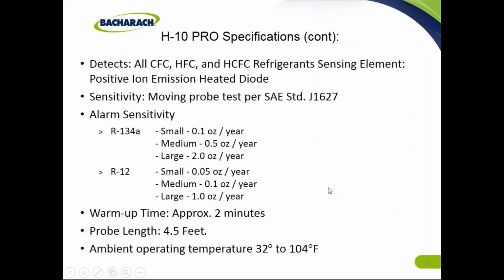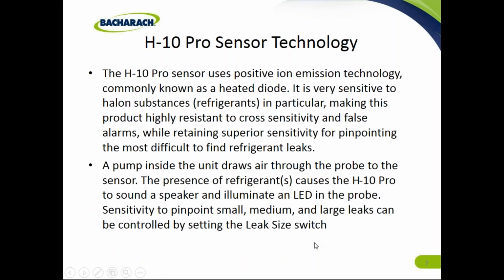We talked about all the refrigerants that it senses with this positive ion emission heated diode. And here are the sensitivity levels that it will detect for the different gases. We talked about the warm-up time, 2 minutes, probe length, 4.5 feet, and the temperature, 32 to 104. The H10 Pro sensor uses a positive ion emission technology, commonly known as a heated diode. It is very sensitive to halon refrigerants in particular, making this product highly resistant to cross-sensitivity and false alarms, while retaining superior sensitivity for pinpointing the most difficult to find refrigerant leaks. A pump inside the unit draws air through the probe to the sensor. The presence of refrigerant causes the H10 Pro to sound a speaker and illuminate an LED in the probe. Sensitivity to pinpoint small, medium, and large leaks can be controlled by setting a leak size switch.